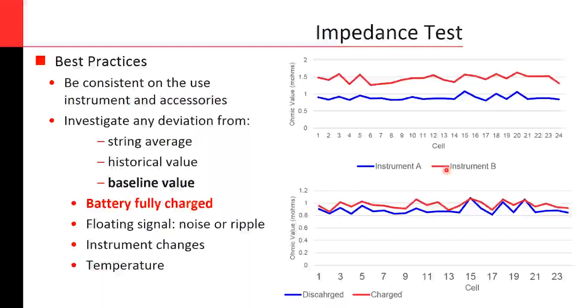As best practices for impedance test, again, be consistent on the use of the instrument and the accessories. This test is highly dependent on the type of instrument that you use and the accessories that you use. Any deviation in the value that you measure, you should investigate that deviation comparing to the string average. If you only have one measurement, you can still start doing some analysis by establishing the average of all the string and comparing to that. You can compare also to historical values, like a previous test or the trend that you have from previous tests, or you can establish a baseline value.